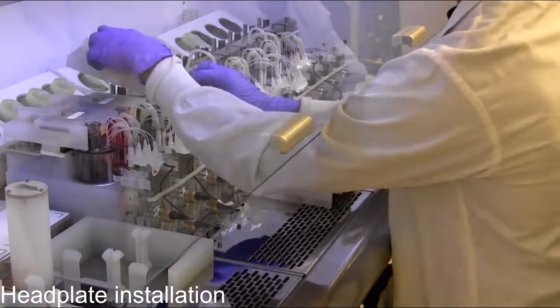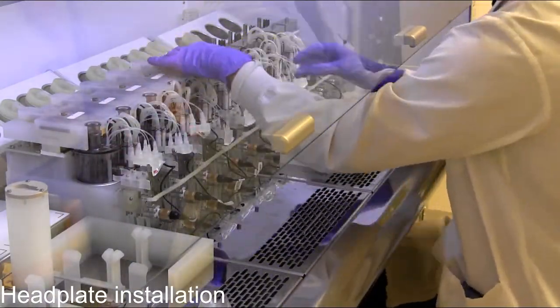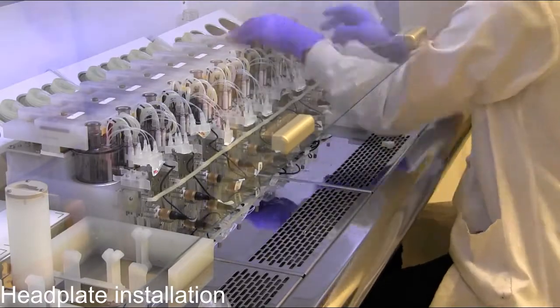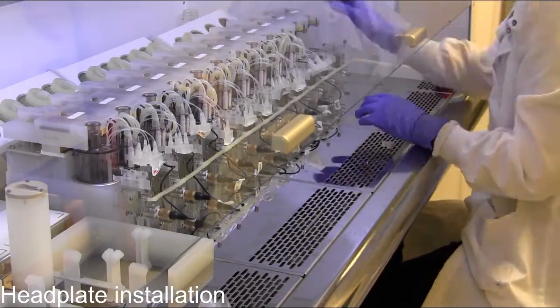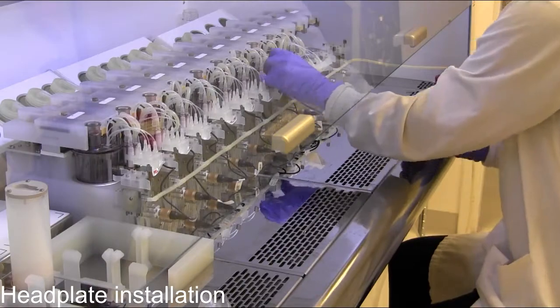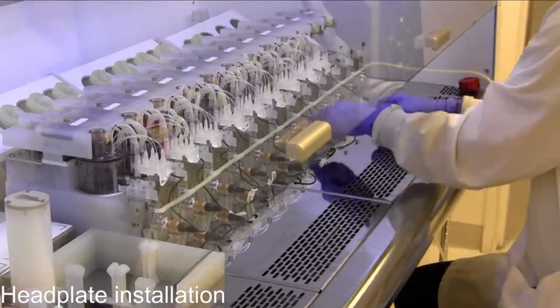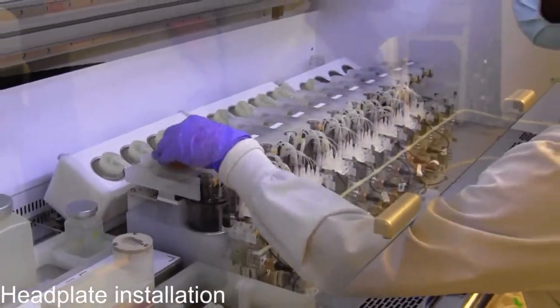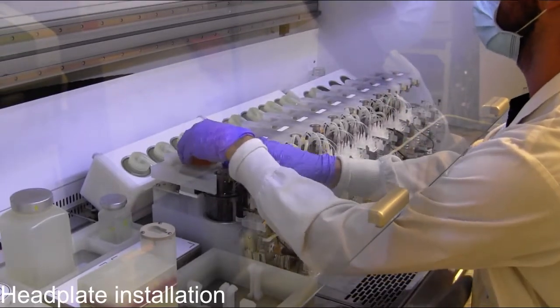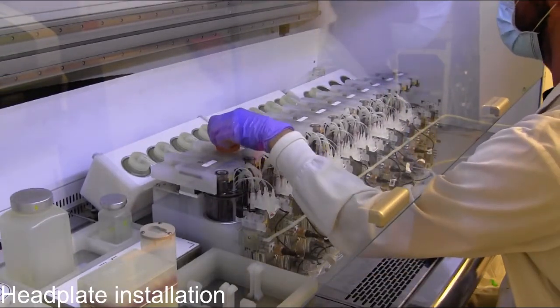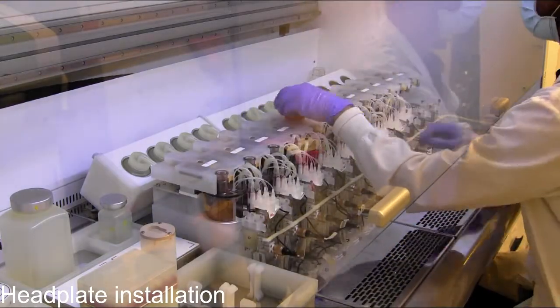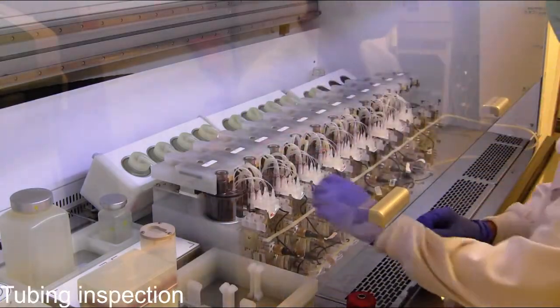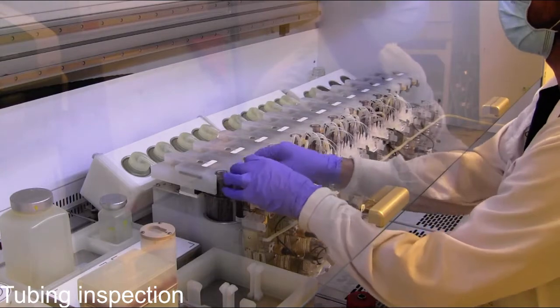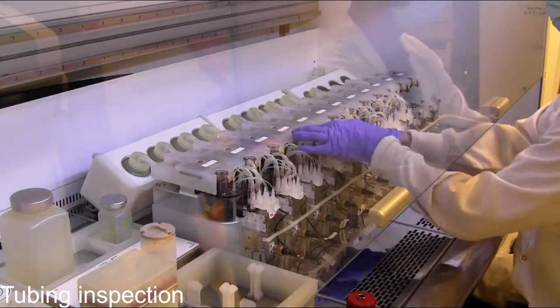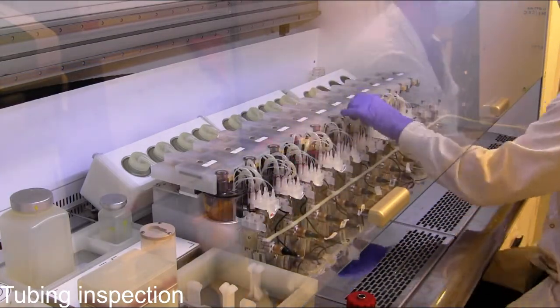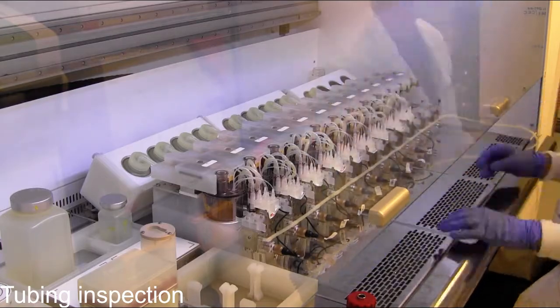Install the head plates to complete the bioreactor loading step. Finally, inspect the exhaust gas line for pinch points and loose connections, while ensuring the lines are positioned so that they will not interfere with the liquid handler during the experiment.